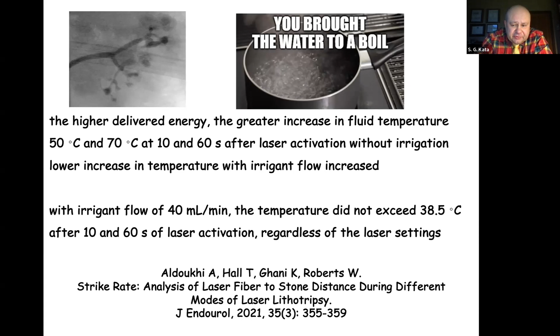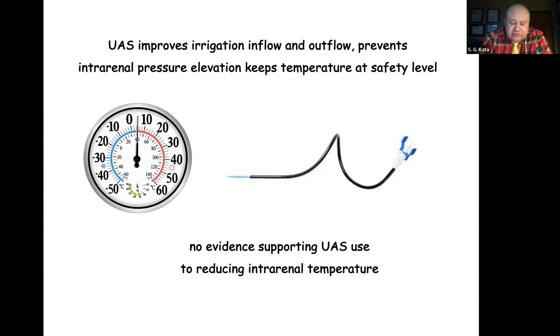And what's also important, we know that when we increase irrigation flow, we are decreasing temperature within the collecting system. And with an irrigant flow of 40 milliliters per minute, temperature does not exceed 38 or 40 Celsius. As we discussed, the access sheath improves irrigation flow, outflow, and prevents an increase in intrarenal pressure. So we would suspect that it should also allow us to control temperature within the collecting system. However, there is no evidence supporting that the ureteral access sheath can be used to reduce intrarenal temperature.